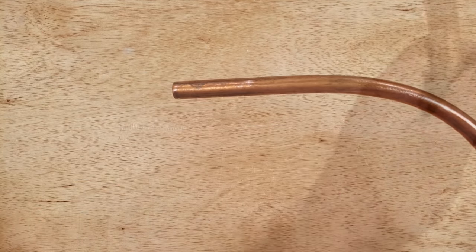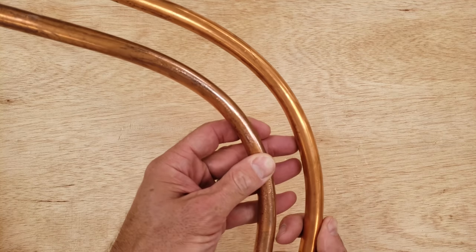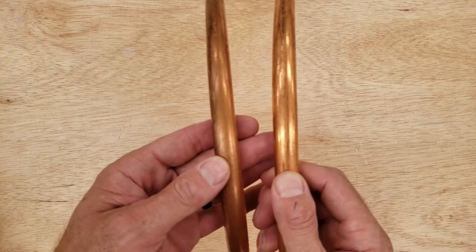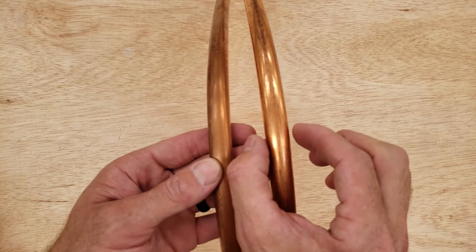Here's the difference between these two pipes. This one was the hand bent one, and this one was the spring bent. You see the hand bent is a little wider, but there's no kinks, that's not a problem.